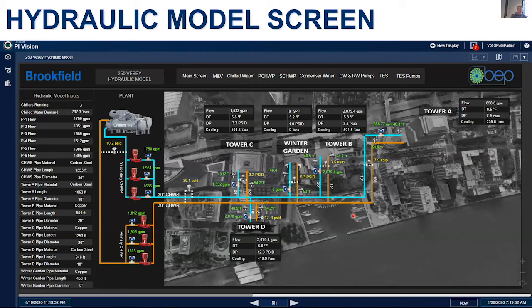And we have a lot of district thermal customers, and they like this because if they have to add a building, it's not like, hey, call up ABC Engineering, let's dust off the old hydraulic model, let's rerun it. If it's constantly running, I'm going to know, hey, let's just do a pull down here, see when we peaked velocity on this pipeline. Yep, we got room. Our standard, 11 feet per second, is our maximum velocity. We're good. We peaked at like 9 three years ago. We got room.